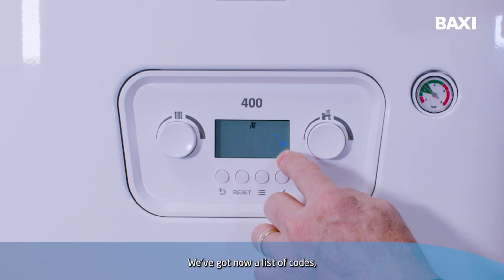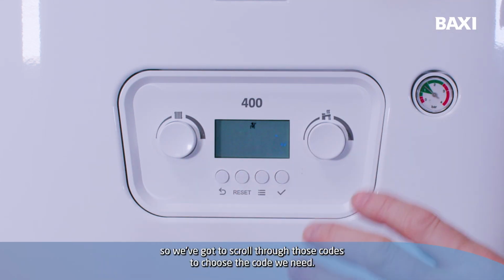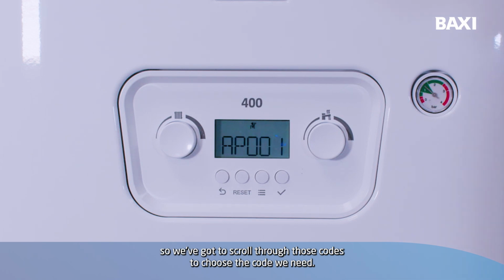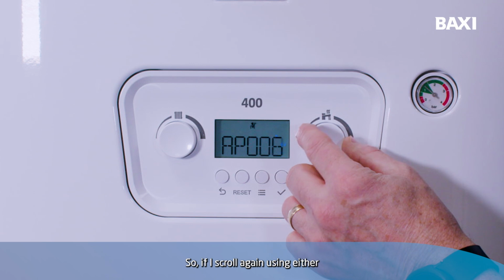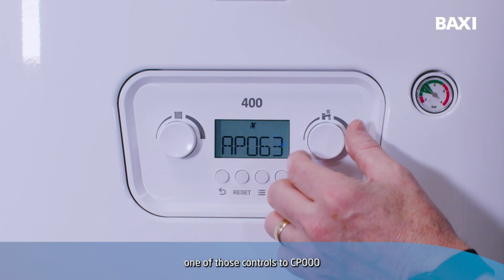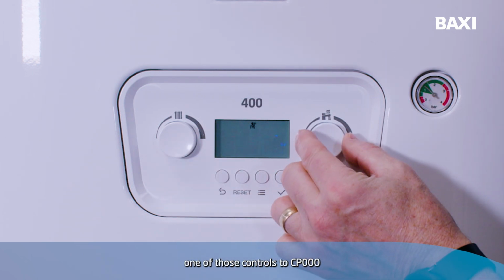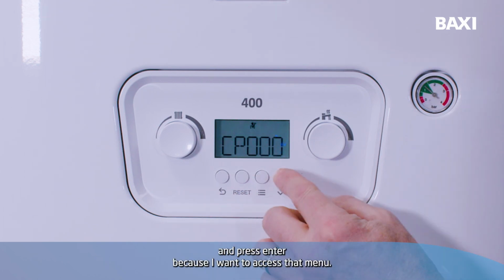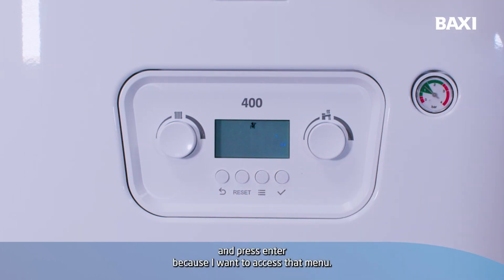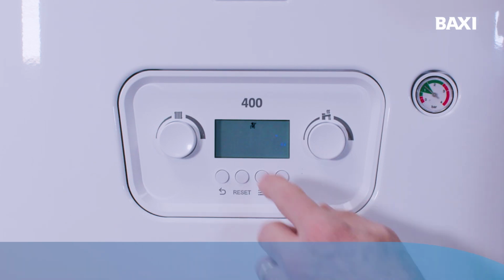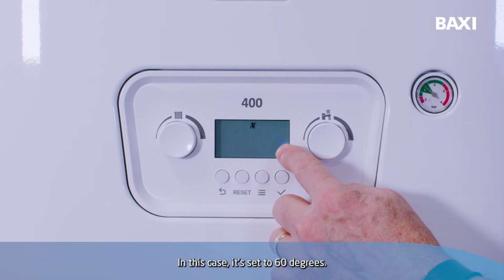We've got now a list of codes, so we've got to scroll through those codes to choose the code we need. In this case, we're going to look at something called CP000. So if I scroll again using either one of those controls to CP000 and press enter because I want to access that menu, what this is going to give me is my heat output to my heating system. In this case, it's set to 60 degrees.